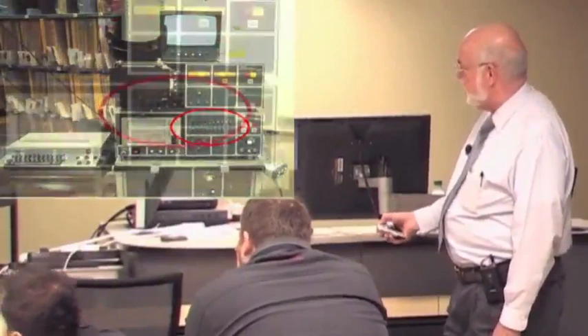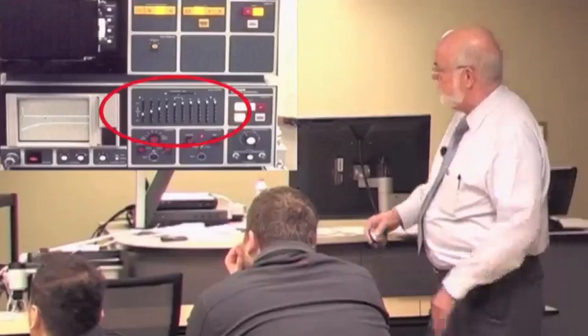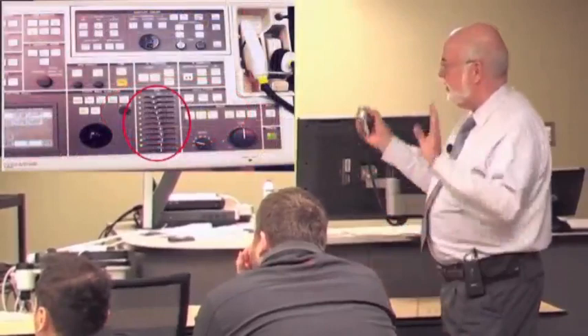So going back to our first piece of equipment here at Tech, you can see it has this thing, and you can see the knobs set that we're actually, this is one of those TGC controls where we're compensating for the fact that we lose energy as we go deeper. This, again, from that Toshiba unit that had the color and the black and white monitor, same idea.